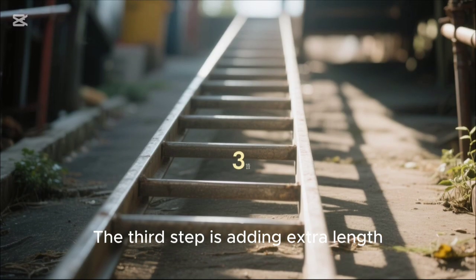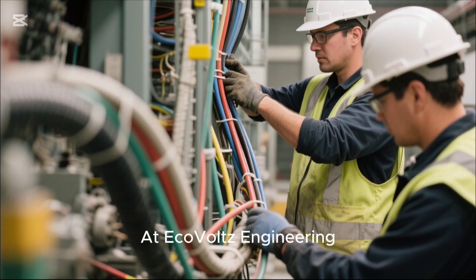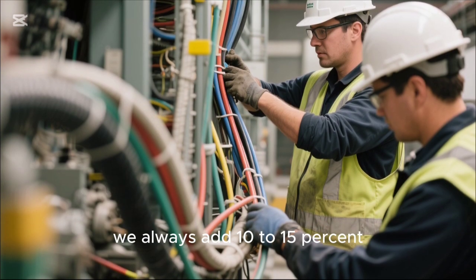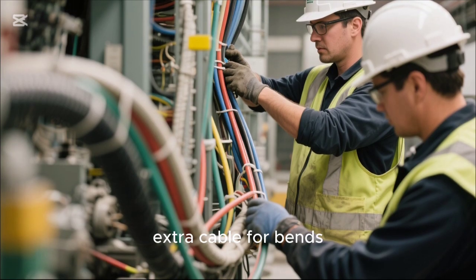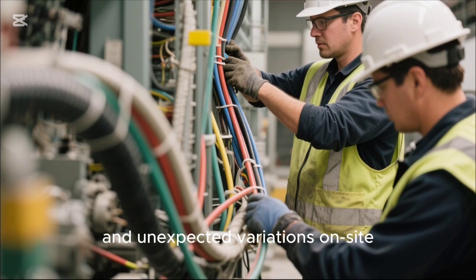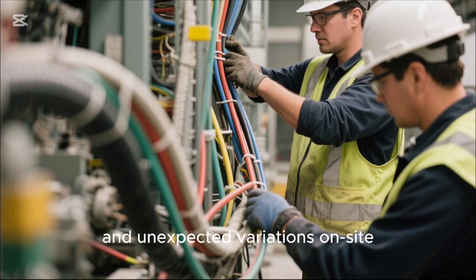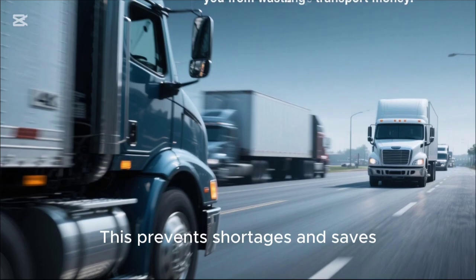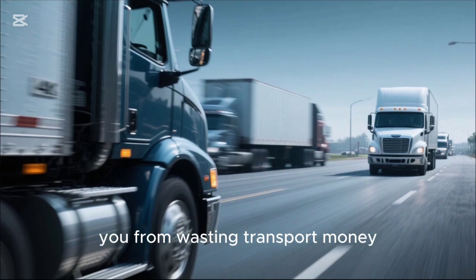The third step is adding extra length. At EcoVoltz Engineering, we always add 10 to 15% extra cable for bends, routing adjustments, and unexpected variations on site. This prevents shortages and saves you from wasting transport money.